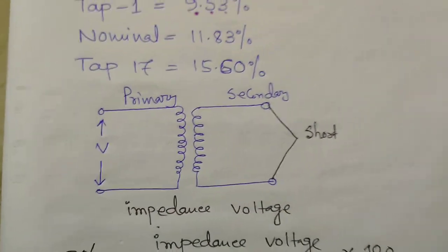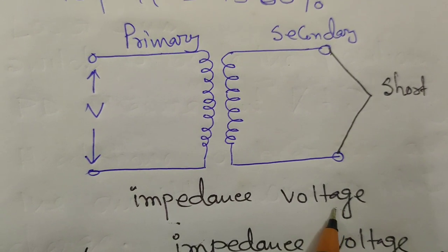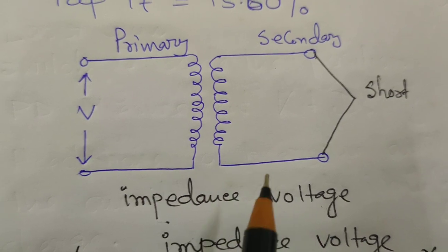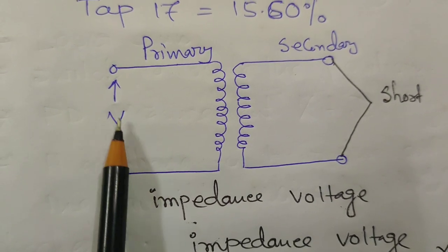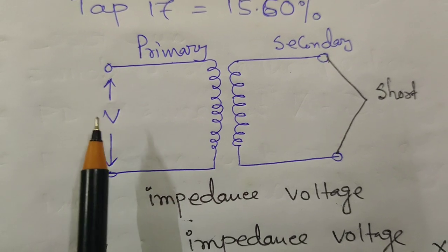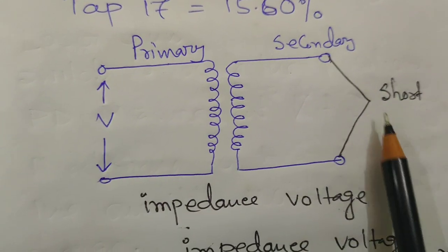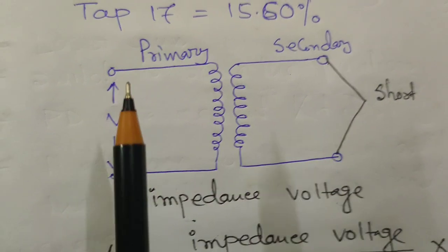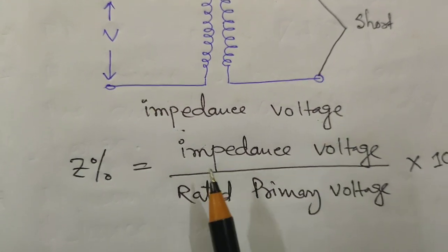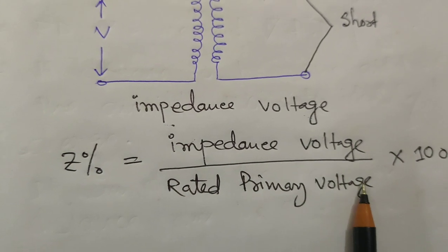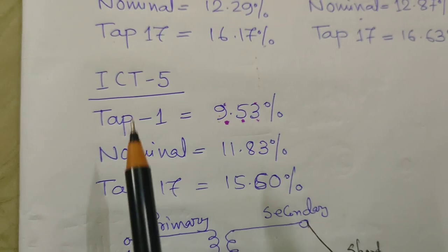Now let's discuss what percentage impedance is. First, you have to identify the impedance voltage. To calculate the impedance voltage, you short the secondary side of the transformer and apply a minimum voltage to the primary side. When the rated current of the transformer flows at the secondary side, that applied voltage is considered the impedance voltage. Then you divide the impedance voltage by the rated primary voltage and multiply by 100 to get the percentage impedance.